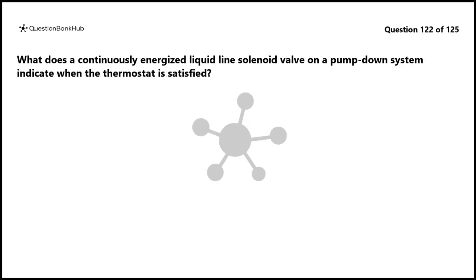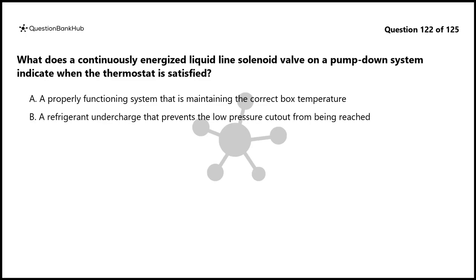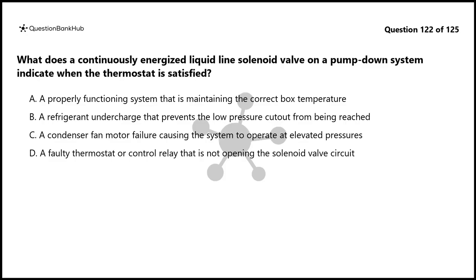Question 122. What does a continuously energized liquid line solenoid valve on a pump-down system indicate when the thermostat is satisfied? A. A properly functioning system that is maintaining the correct box temperature. B. A refrigerant undercharge that prevents the low-pressure cutout from being reached. C. A condenser fan motor failure causing the system to operate at elevated pressures. D. A faulty thermostat or control relay that is not opening the solenoid valve circuit.